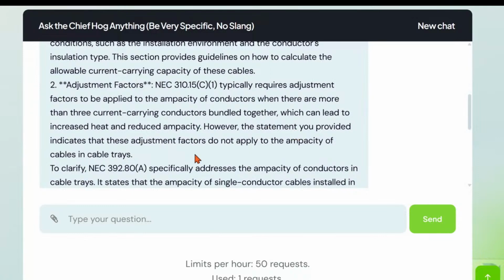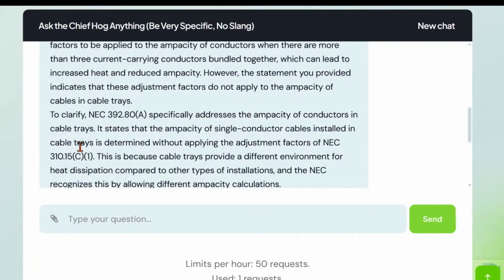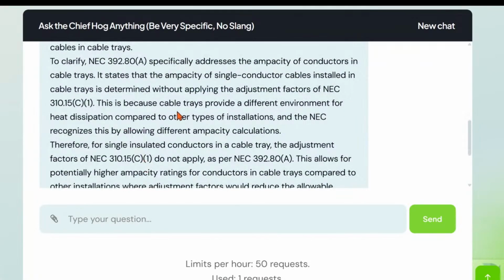However, the statement you provided indicates that these adjustment factors do not apply to the ampacity of cables in a cable tray. To clarify, 392.80(A) specifically addresses the ampacity of conductors in cable trays. It states that the ampacity of a single conductor cable installed in cable trays is determined without applying the adjustment factors in 310.15(C)(1). This is because cable trays provide a different environment for heat dissipation compared to other types of installations, and so on.